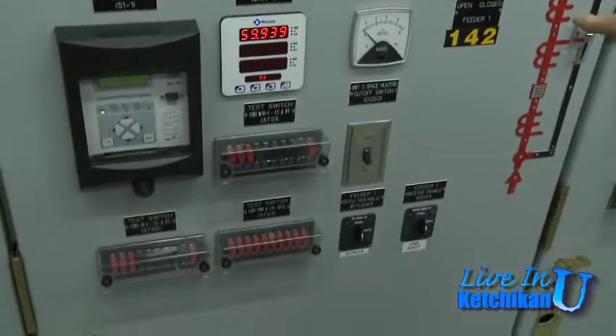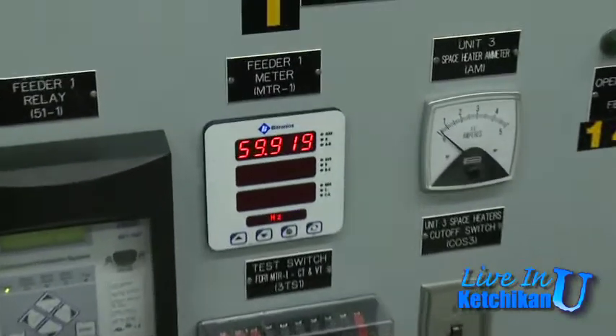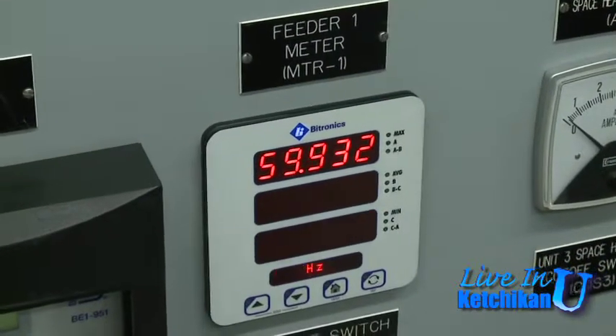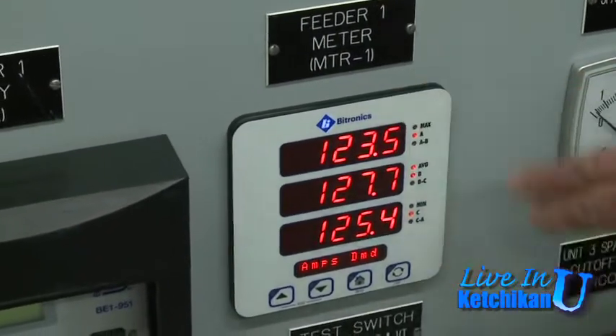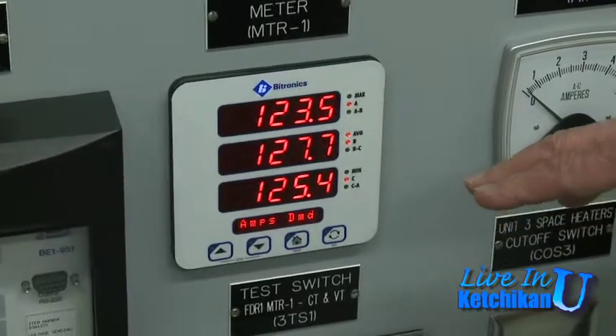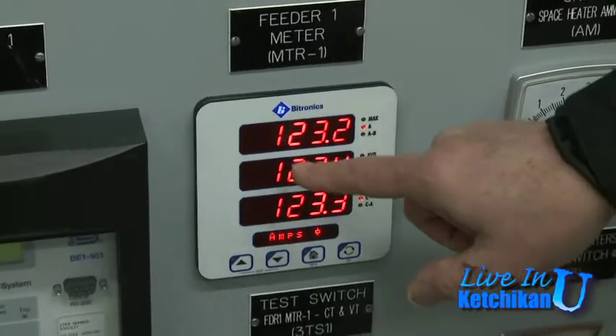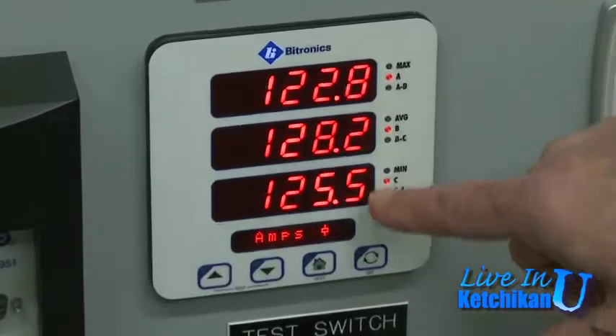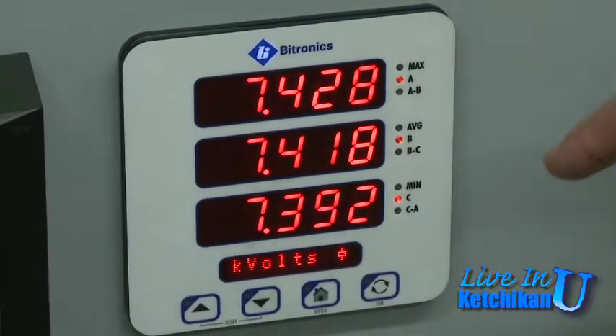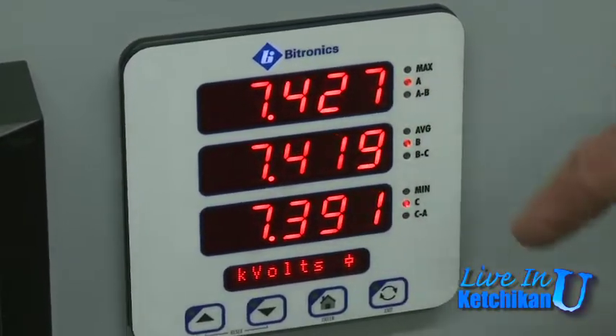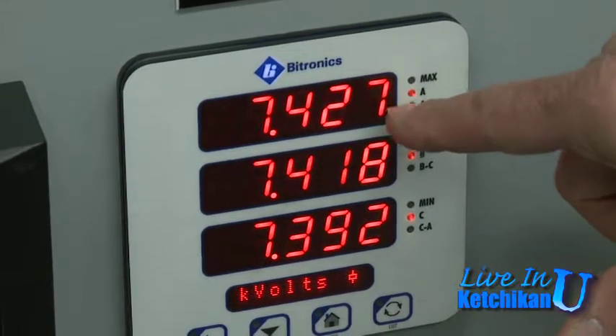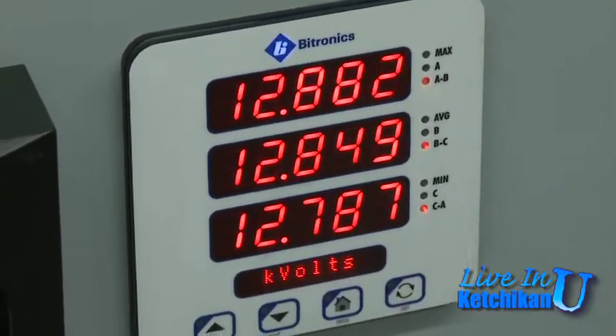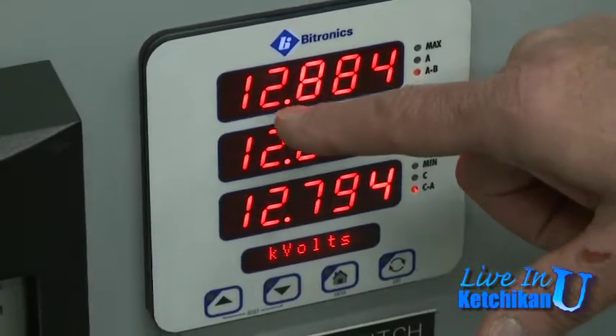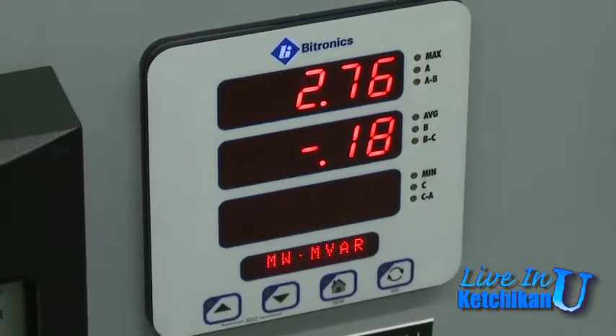Sure, you were talking about the numbers going up and down, is that what that's doing? Well, this is a meter, and this meter gives us a bunch of data. It tells us the amps on each one of the legs, each one of the phases. It cycles through and tells us the volts—this is volts to ground, and this is volts phase to phase, 12.884.